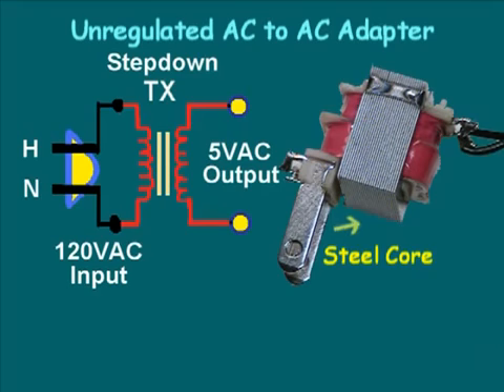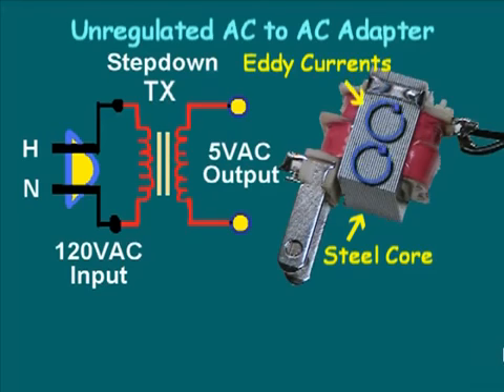The steel core is an excellent conductor of magnetic flux and concentrates the flux for maximum coupling between primary and secondary windings. The steel core is also an electrical conductor, and an alternating magnetic field induces electrical currents called eddy currents within the core. These eddy currents cause the core to heat up. This core is constructed using laminated steel sheets that reduce eddy current losses so the transformer runs cooler.